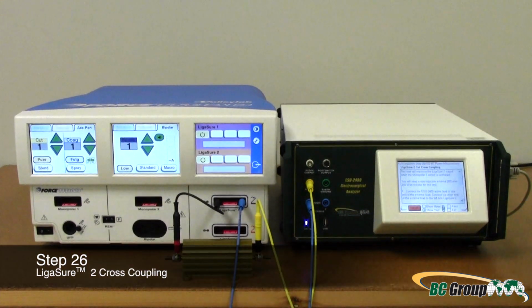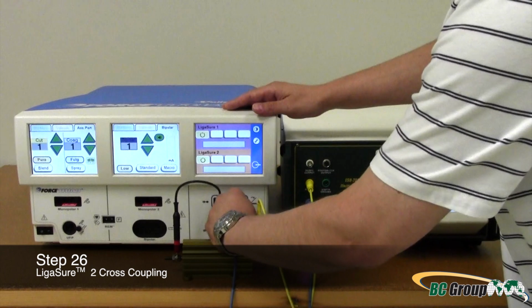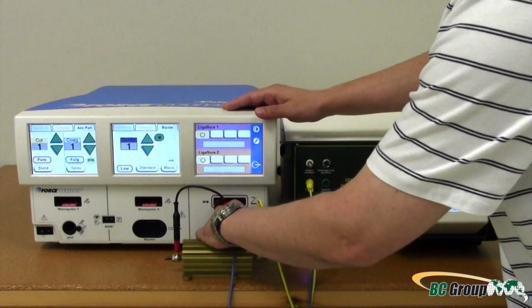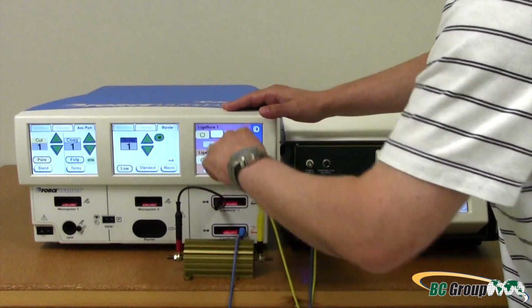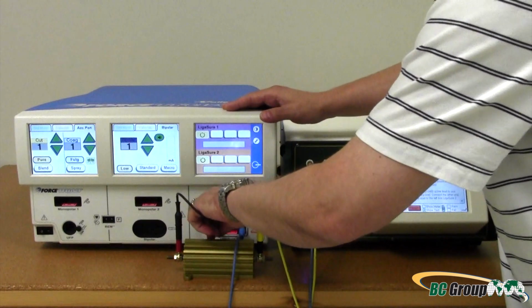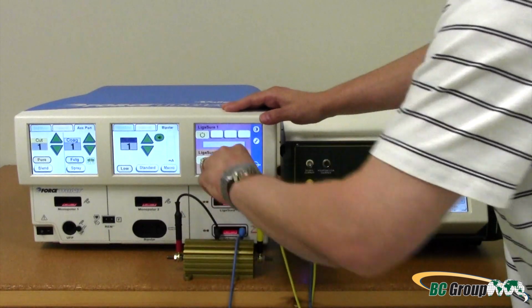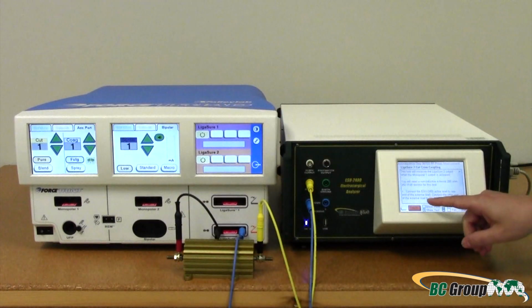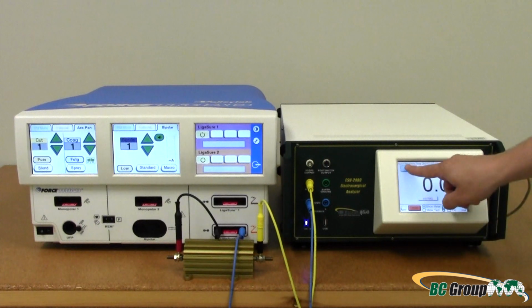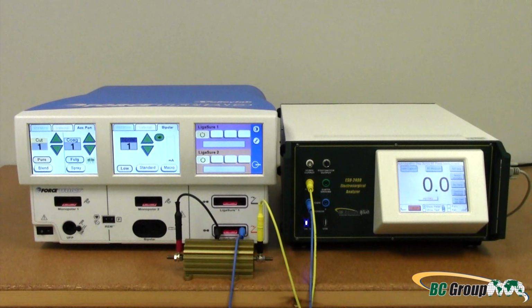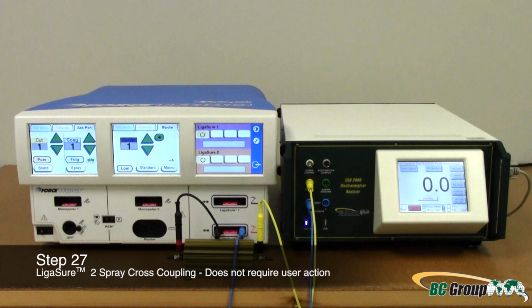Step 26. LigaSure 2, cross-coupling. Move the dispersive lead from the LigaSure 1 output to the right tine of the LigaSure 2 output. Move the short jumper to the left tine of the LigaSure 2 output. Select Show Meter and then press Capture. Step 27 does not require user action.